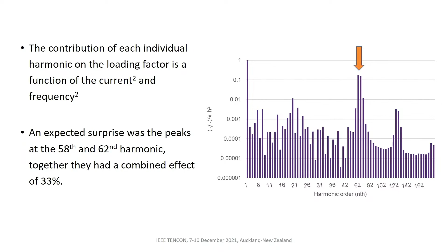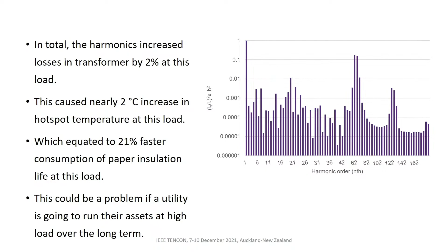Now, in terms of the transformer itself, there wasn't really that much happening in it. Maybe there was a 2% increase of load, and then we calculated a 2-degree increase in hotspot temperature. Now, 2 degrees probably sounds not that much, but that does mean it's ending up around 21% faster consumption of paper during daylight hours. So in terms of what it means for the transformer, if something is being run at quite a high load, and then we add 21% faster aging during daylight hours, then that can be pretty significant. Whereas if it was not really that loaded, then it might not really do much.